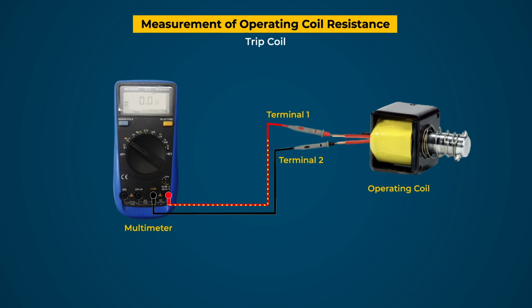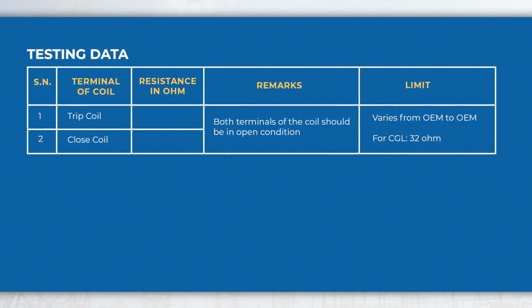Finally, a current will flow from the ohm terminal to the common terminal of the tester, and it calculates the resistance of the coil by Ohm's law. Testing data may be recorded in the format given below for evaluation and future reference.